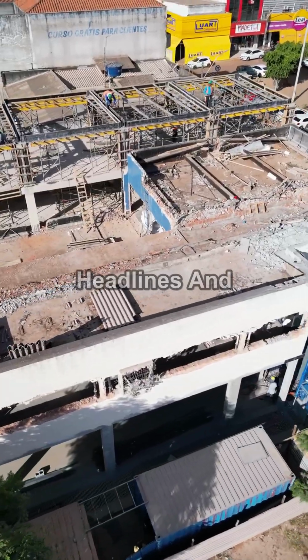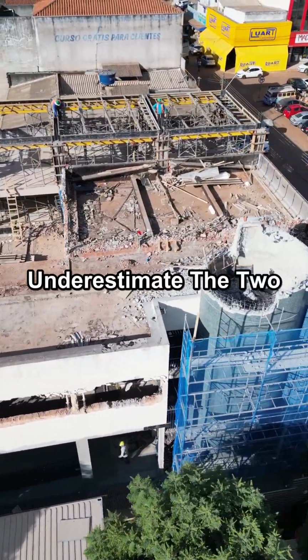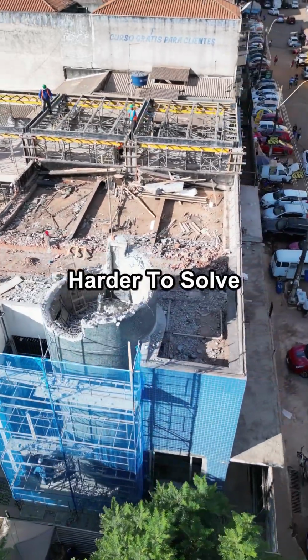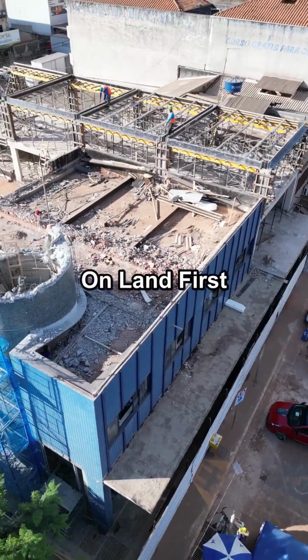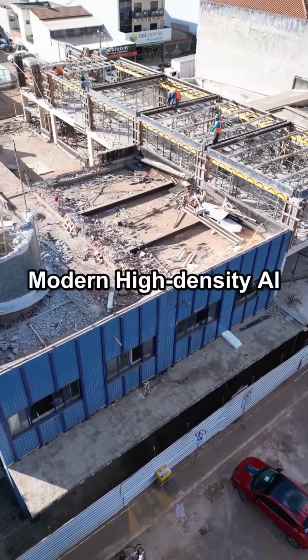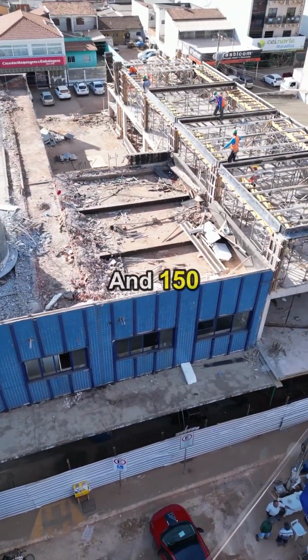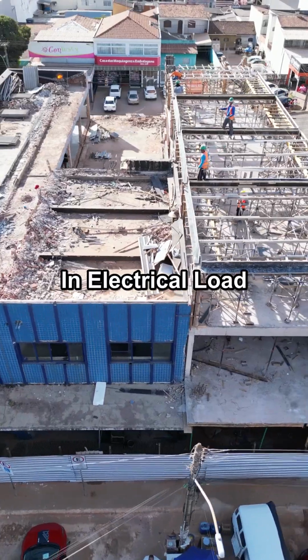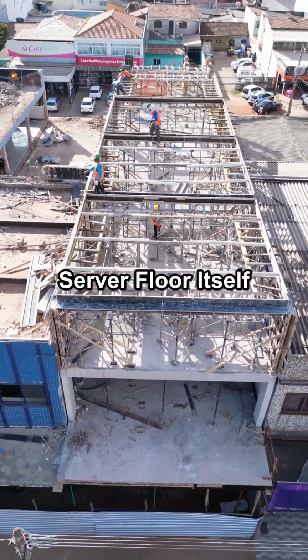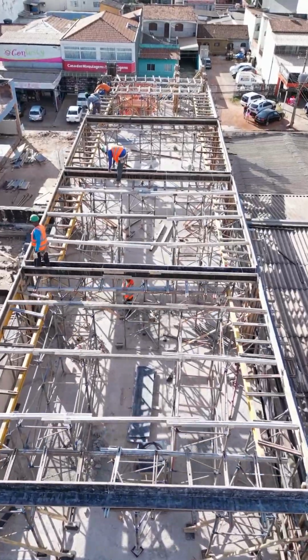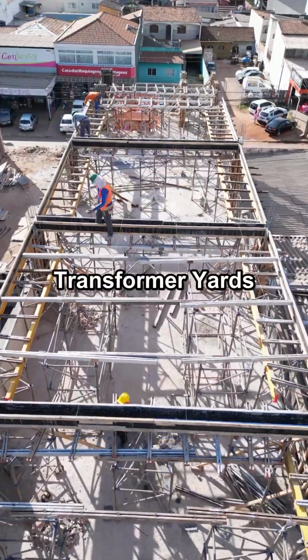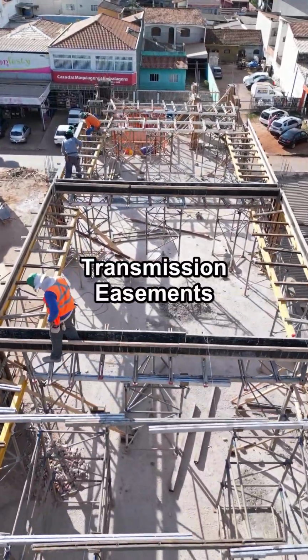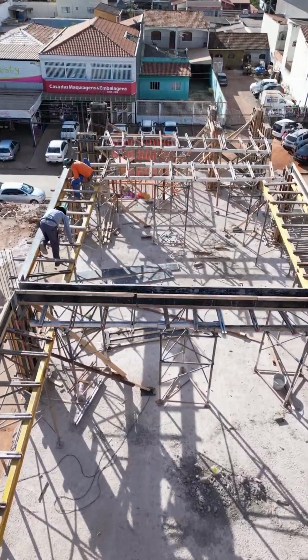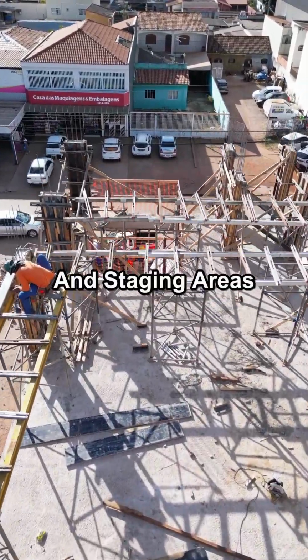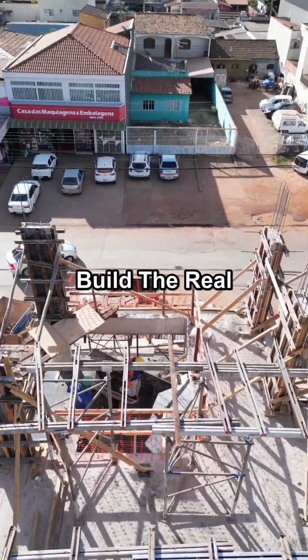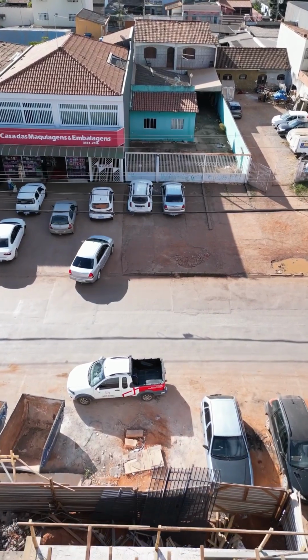People fixate on power headlines and consistently underestimate the 2 physical constraints that are actually harder to solve: land and water. On land first, modern high-density AI compute facilities run somewhere between 50 and 150 megawatts per acre in electrical load density on the server floor itself. But that's just the compute footprint. Once you account for cooling towers, transformer yards, substation pads, transmission easements, drainage infrastructure, mandatory buffer zones, and staging areas for a multi-phase build, the real land requirement per megawatt expands dramatically.